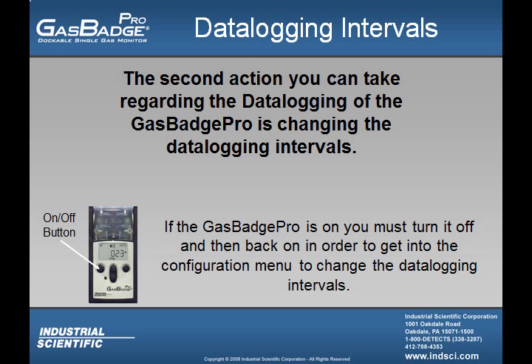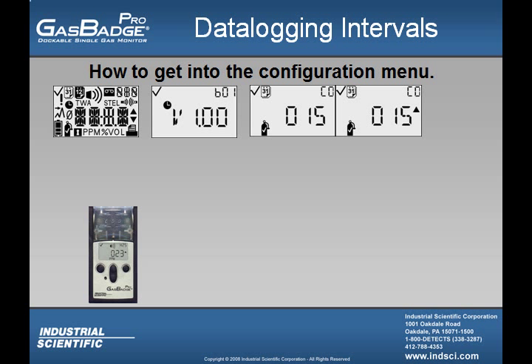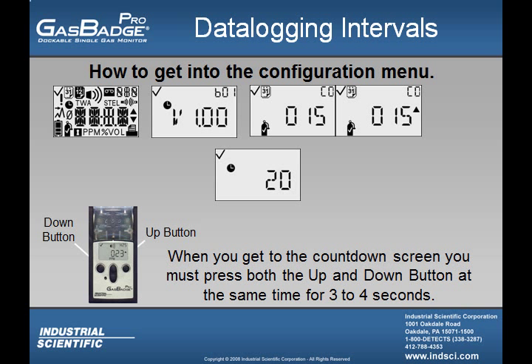The second action the user is able to access is the changing of data logging intervals. If the user is trying to change this value and the instrument is already turned on, they must first turn the instrument off and then back on again in order to get into the configuration menu. Once the user has turned the instrument on, they will see the startup screen showing the revision number, how many days since or until a calibration is due, and the countdown screen. Once the user sees the countdown screen, they must press the up and down buttons at the same time for roughly 3 to 4 seconds to access the configuration menu.